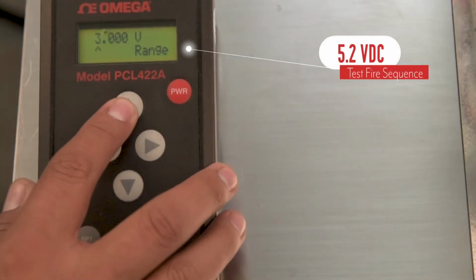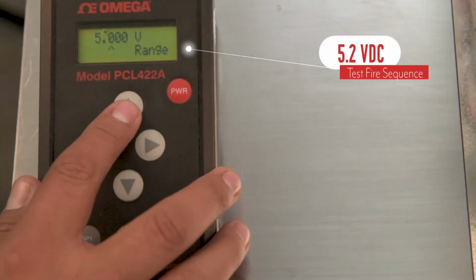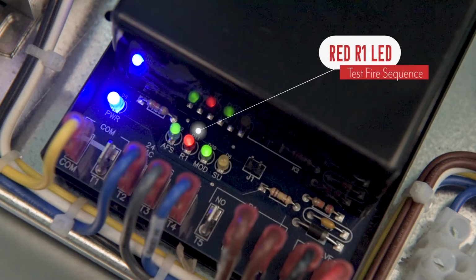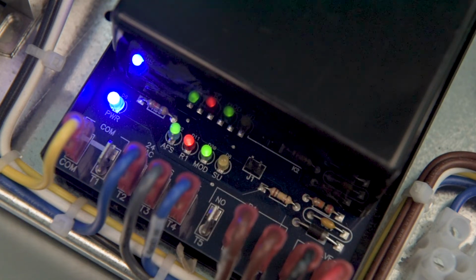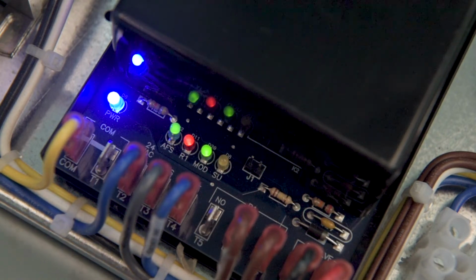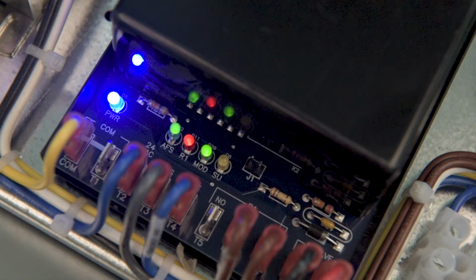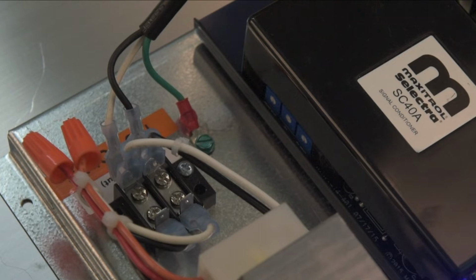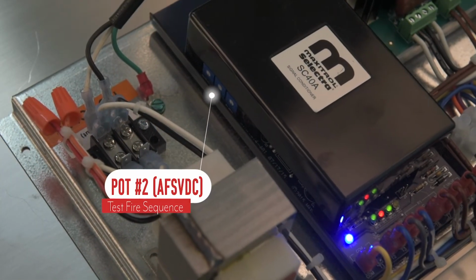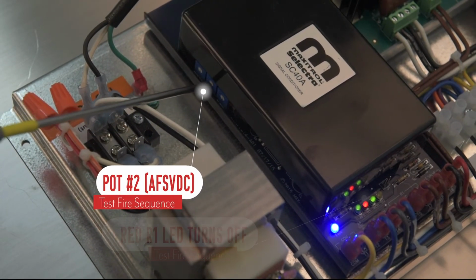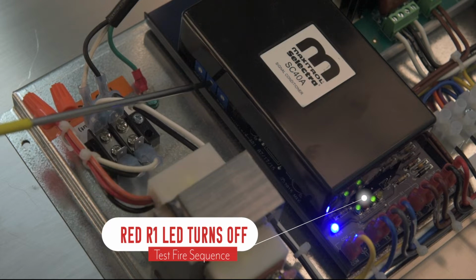Increase the modulation signal to the SC40 to 5.2 volts DC. Verify that the red R1 LED turns off and that the inducer goes to high speed. If the red LED turns off, then continue to high fire position. If the red R1 LED does not turn off, use a flat tip precision screwdriver to adjust pot number 2 labeled R1 on the SC40. Turn very slowly counterclockwise until the red R1 LED turns off. This sets the transition point for the inducer fan speed.